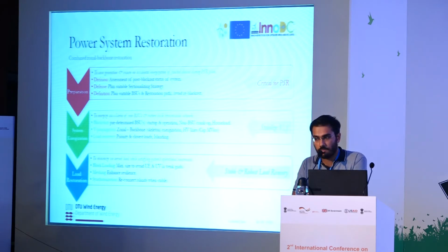Ultimately, the aim is to pick up loads, so some sort of a block load is picked up, which is determined by the operators depending on the system. It can vary from 10 megawatts to 40 megawatts in larger systems. And this is done while, of course, maintaining voltage and frequency in stable operating ranges. And then for resilience, meshing is done, and finally synchronization between all the islands that are stable is done to ultimately have the complete grid.